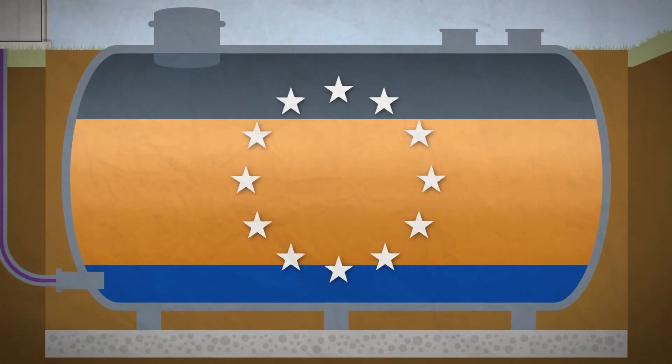To meet European fuel standards, diesel must contain no more than 200 parts per million of water, and water is a primary catalyst allowing the formation of diesel bug.